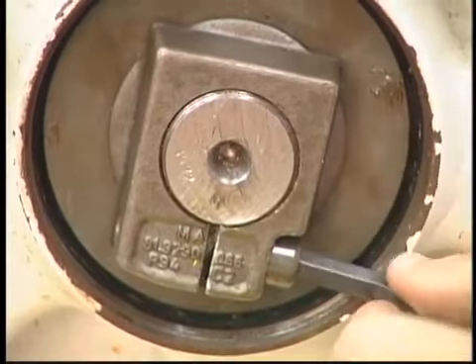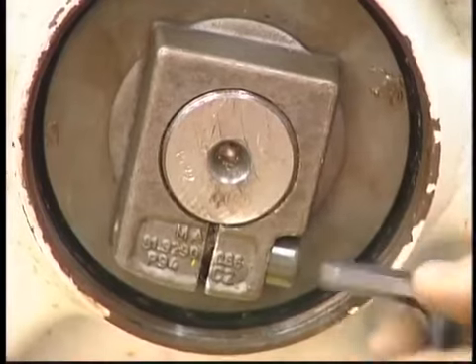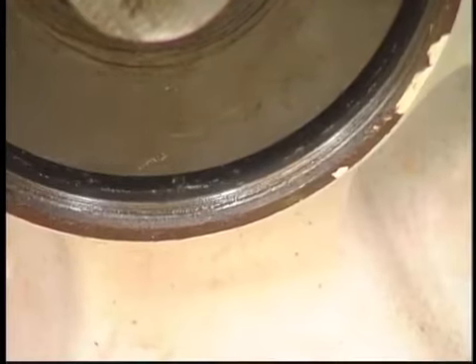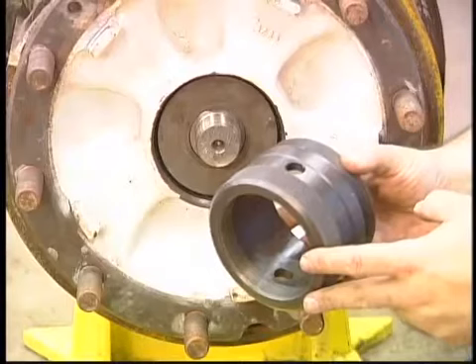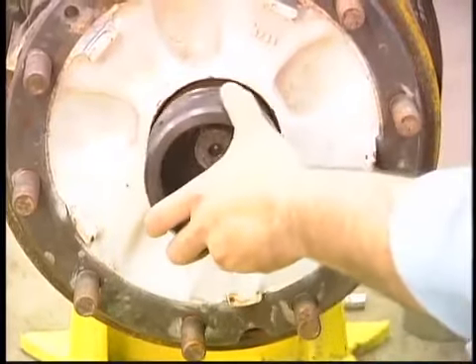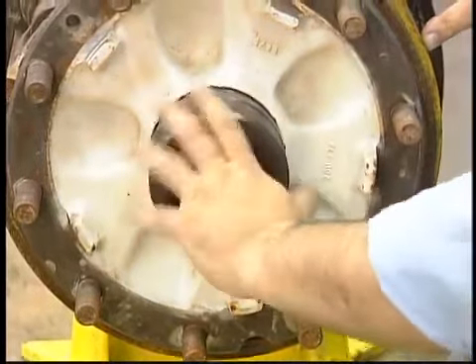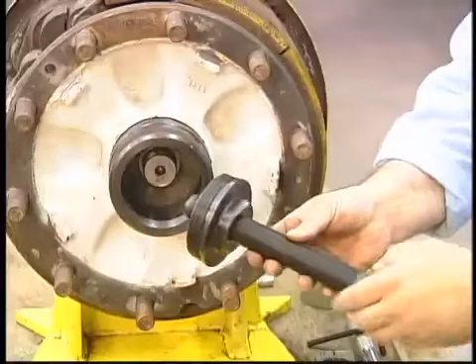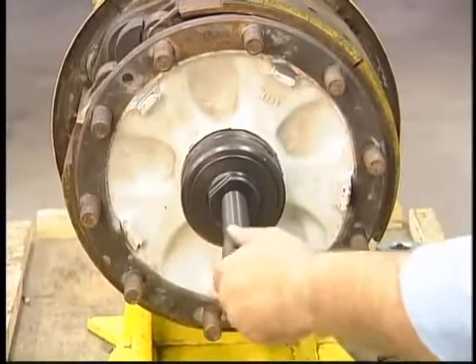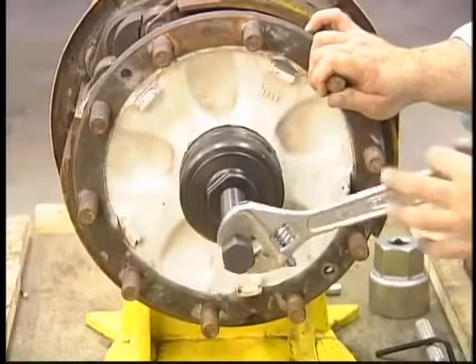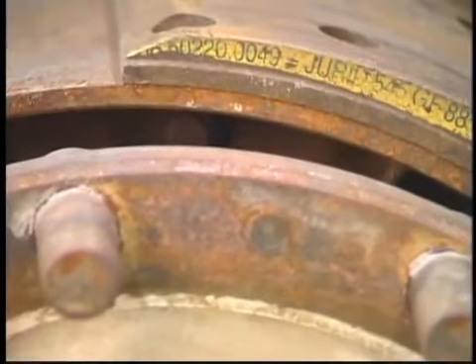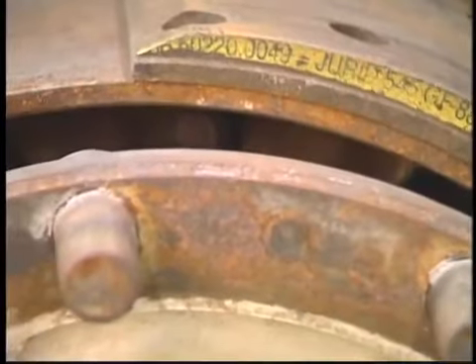Loosen the clamping bolt with an 8mm Allen wrench. Loosen just enough so that the nut can be turned by hand for removal. Inspect the hub threads for any damage. An adapter bushing is used to pull the hub. Thread the bushing in carefully, taking care to avoid cross-threading. Thread the forcing screw into the adapter bushing. Tighten the forcing screw by hand at first and use a wrench once it's tight. As the screw is tightened, the hub will come loose. The hub must travel quite a distance before it is completely loose.